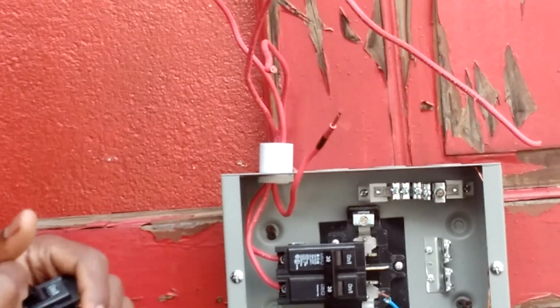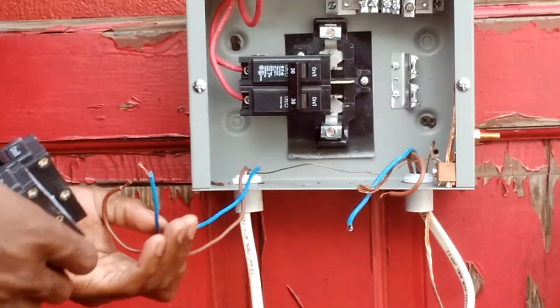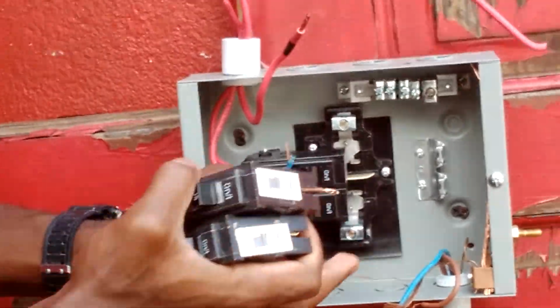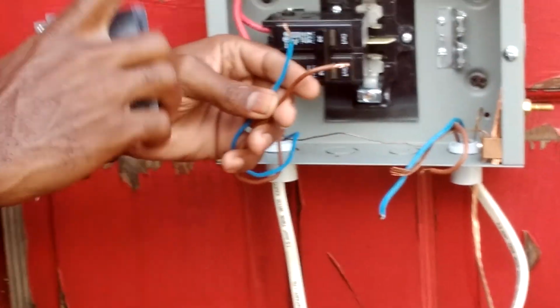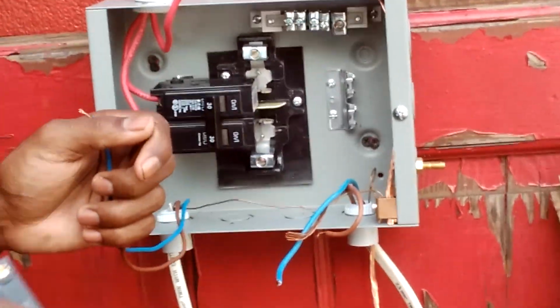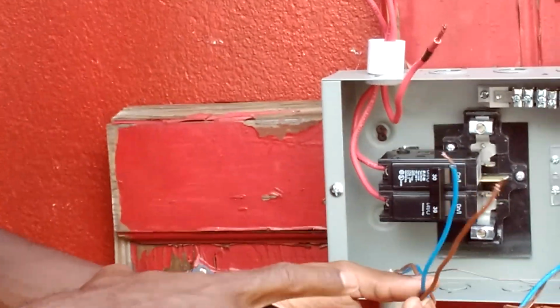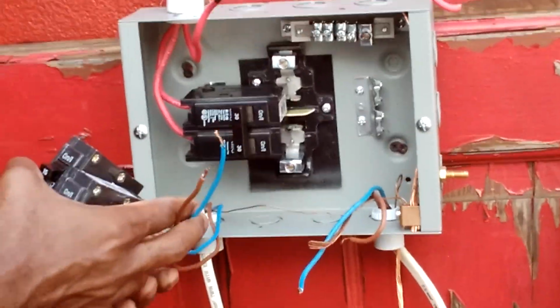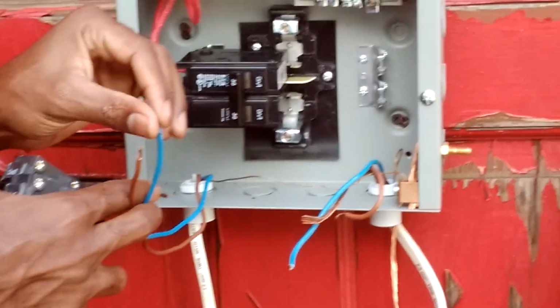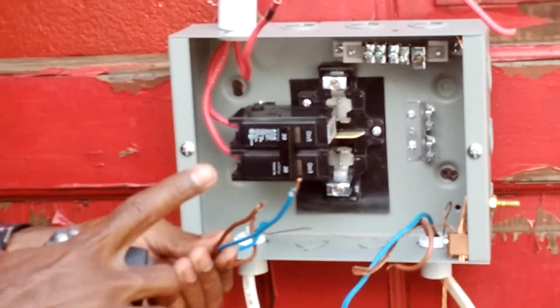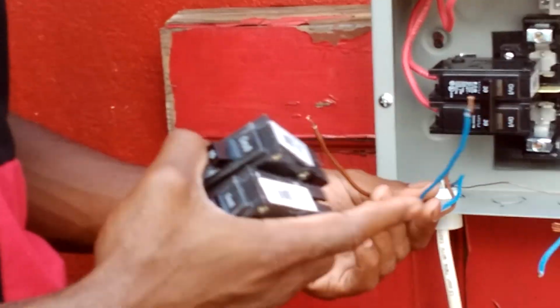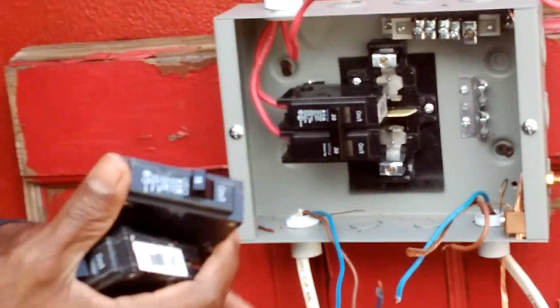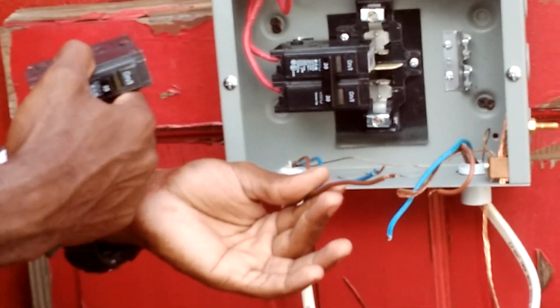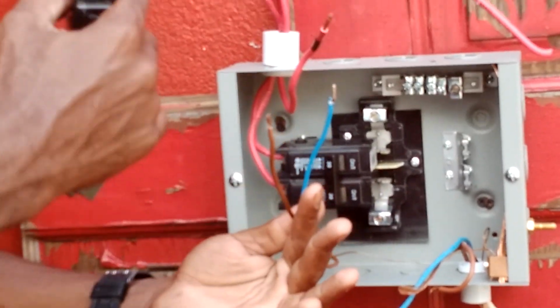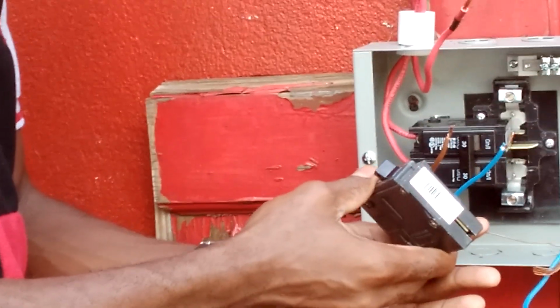This kind of wire is a 1.5 millimeter wire. For my overseas viewers, those in America and Cayman Islands and so on, the 1.5 millimeter wire in the NEC would represent size 14 on the American wire gauge. So we use a 15 amp to protect this, because this wire can go up to 15 amps before it burns. Once it goes over 15 amp, this size wire begins to burn, hence we use a 15 amp to protect this kind of wire.